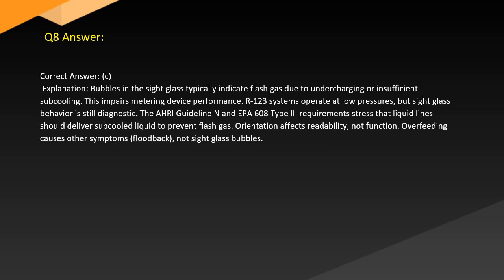Answer. Correct answer: C. Explanation. Bubbles in the sight glass typically indicate flash gas due to undercharging or insufficient subcooling. This impairs metering device performance. R123 systems operate at low pressures, but sight glass behavior is still diagnostic. The guideline and EPA 608 requirements stress that liquid lines should deliver subcooled liquid to prevent flash gas. Orientation affects readability, not function. Overfeeding causes other symptoms, like floodback, not sight glass bubbles.